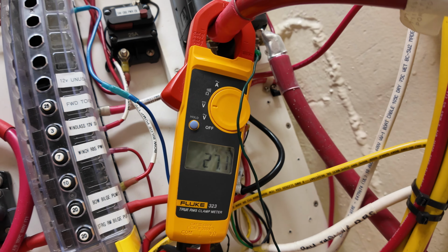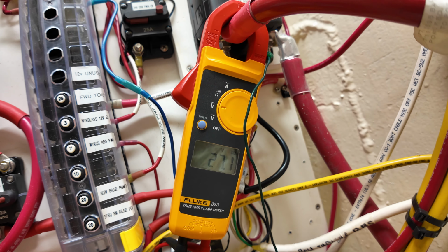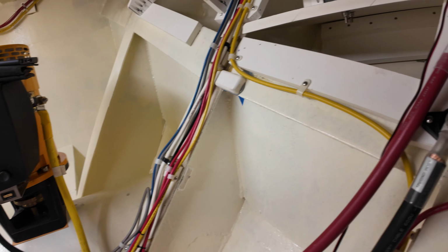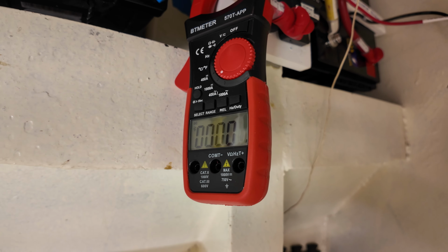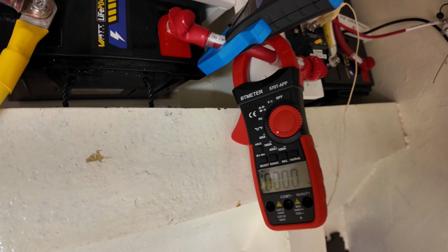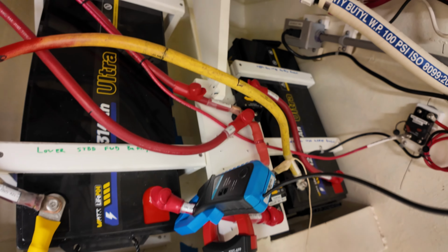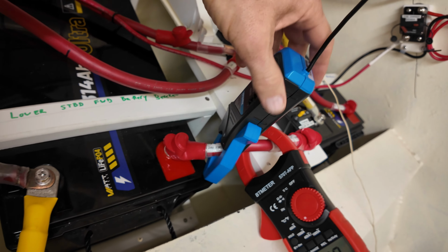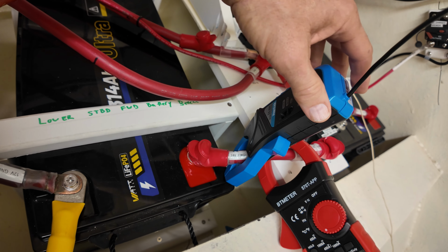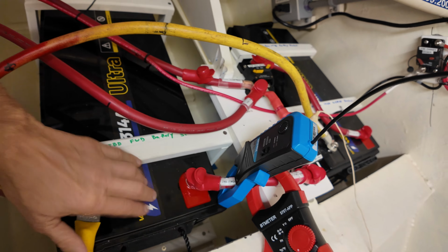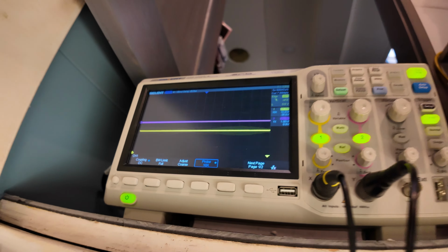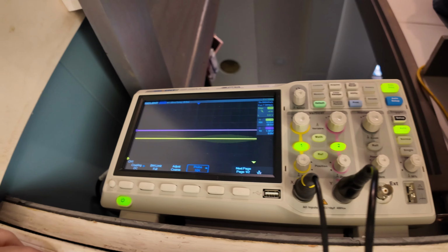So I've got several different instruments going. That guy shows 27 volts, which is a charged 24 volt system. Got the meter that will read current every half second to see if it gets any triggers. And then finally we have the oscilloscope probe right here to read the current coming out of this one battery, which will be displayed up on that screen.